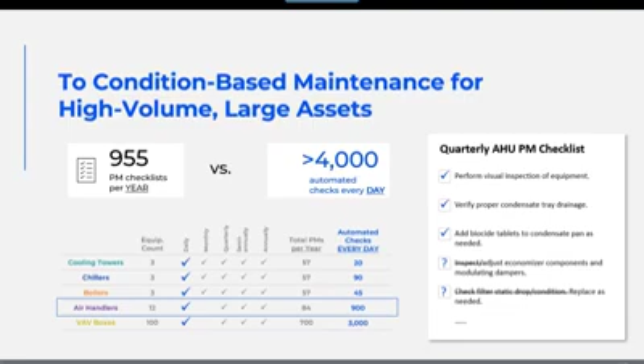So things like filter changes, right? Instead of just going out blindly and replacing filters on a quarterly basis, can we have a differential pressure sensor across the filter bank to tell us when the filter needs to be replaced? Control service, right? We will calibrate all the airflow sensors once per year. Well, what if that doesn't have to be done, right? We can have the data, the FDD tool, tell us when a sensor goes out of calibration, so that we're going out there as needed instead of on a blind schedule basis. That's the type of condition-based maintenance approach that's available on these high volume, large assets.